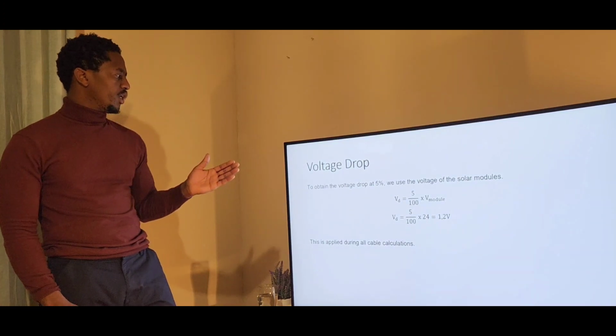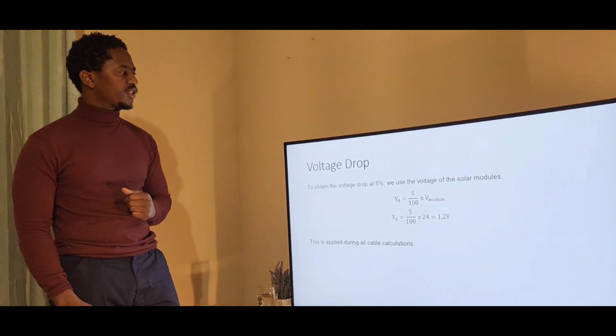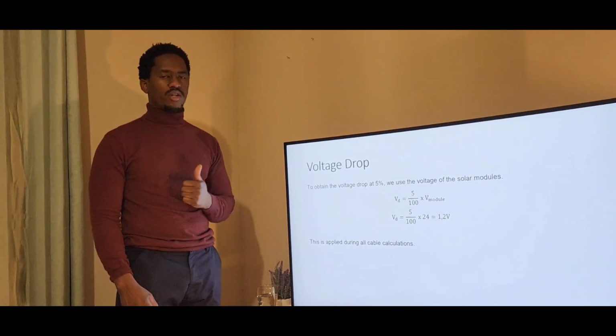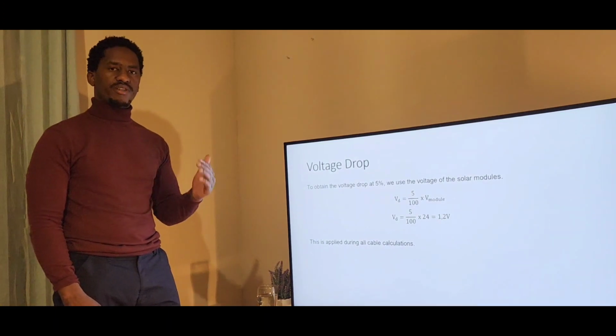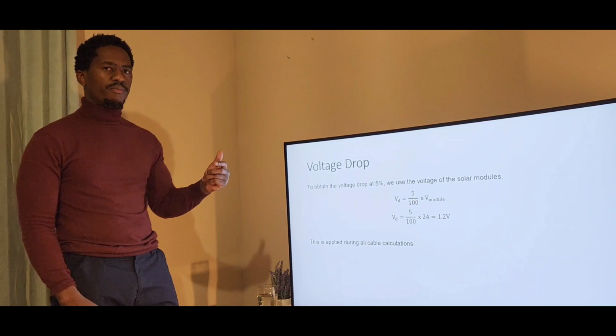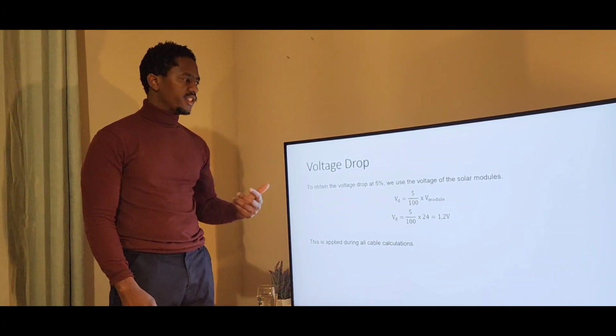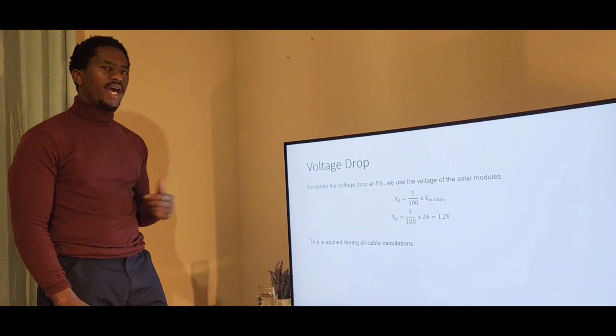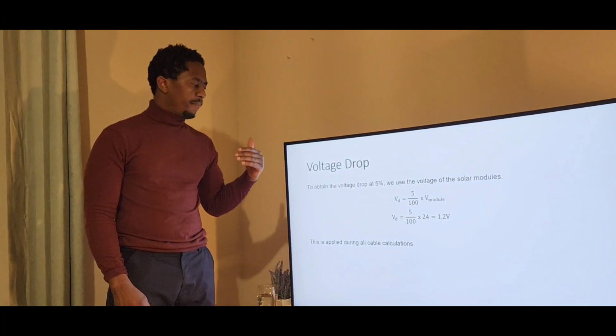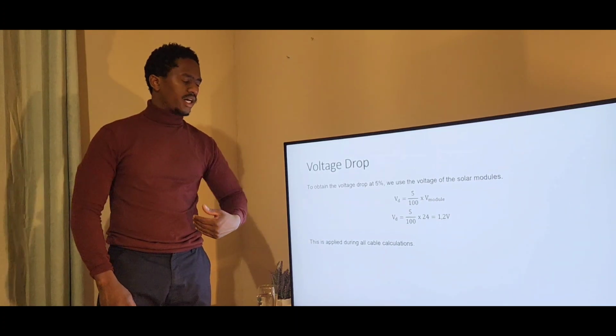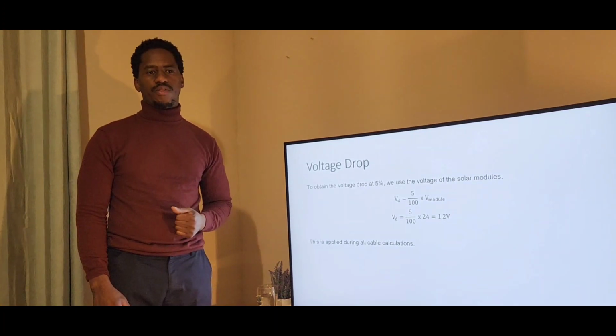Voltage drop. To obtain the voltage drop at 5%, we use the voltage of the solar modules, which is 24 volts. So the voltage drop that is allowed in the system is 1.2 volts. And this is applicable to all the cable calculations throughout the report.